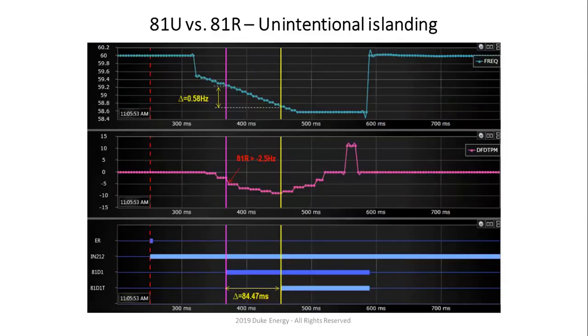So in order to show you a little bit better, I have actually zoomed one of these responses, right? So look at the top. That's our typical frequency. Somebody asked about frequency settings. It's 59.3 on the under frequency and 60.5 on the over frequency where we detect. So if you take a look on the top, you can clearly see the pink line. It's kind of showing when the 59.3 setting is picking up, right? That's your 81D1. We actually have time delay, which is about 5 cycles. So you can see on the bottom 81D1T when that thing times out.